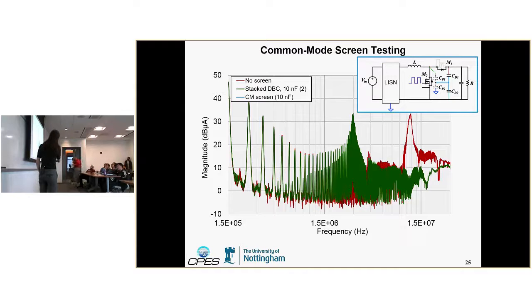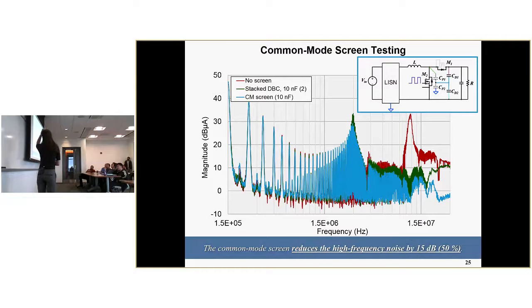But if you take the added step to connect those two, connecting that middle metal layer to half the DC bus, you get even further reduction in the noise at high frequency. For this example, we got 15 dB reduction, which was about 50%.